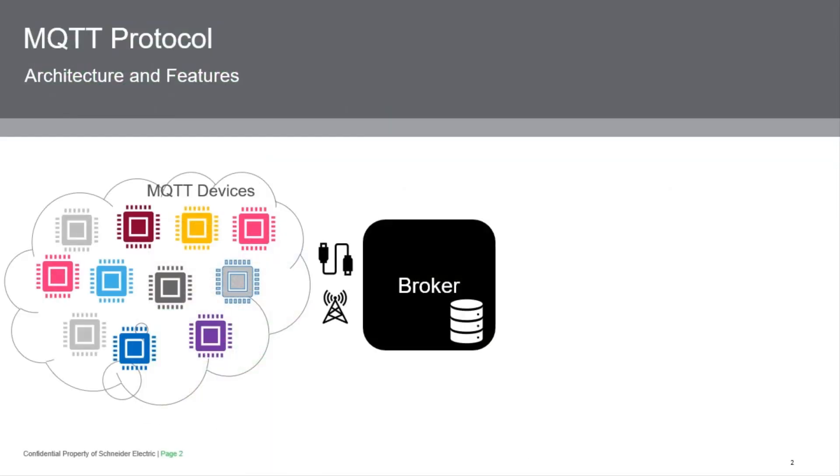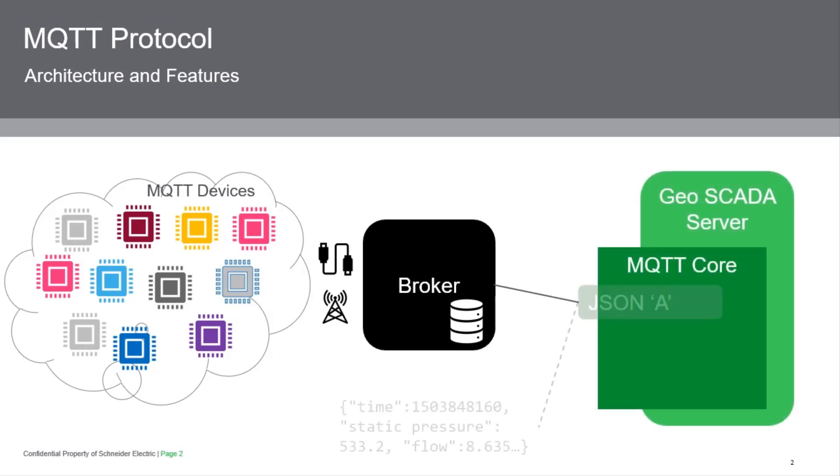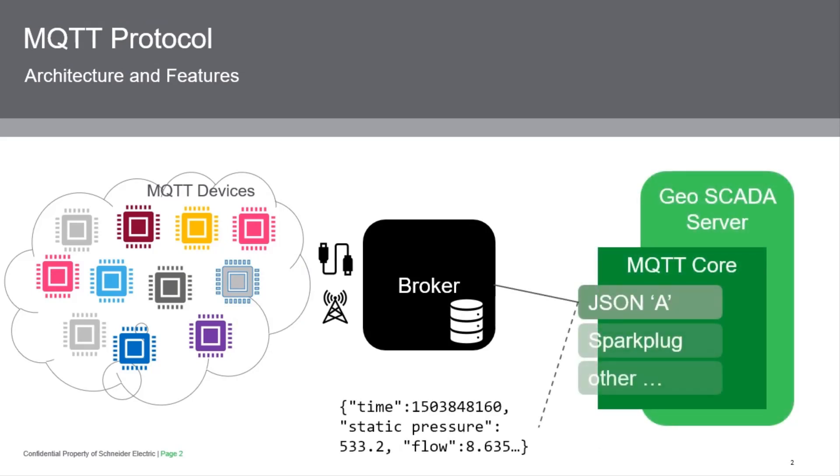With MQTT, a cloud of devices are connected to a broker, which is a third-party software process. Most broker software is open source. The GeoSCADA MQTT driver connects to the broker and subscribes to data coming from the devices. The MQTT protocol itself doesn't specify a content for the data, so to kickstart this in GeoSCADA Expert, we designed a simple format we call JSON-A. You can see this simple text data format, which contains a time value and a list of point names and values.